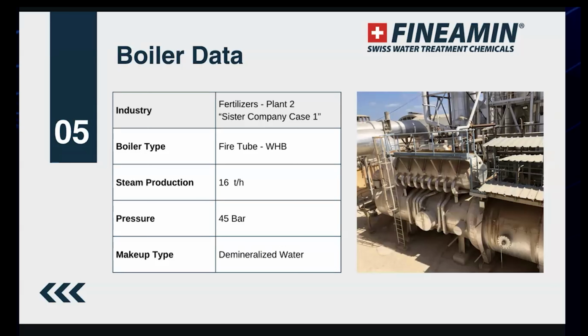Mustafa: Well, if you let me extrapolate the question, if I understand it from a different perspective. If the question is generally about overdosing, there is always a concern about something called gunk formation, or a kind of polymerization, some polymeric structure that will be happening. The good news is that in our general product formulation we are not using octadecylamine, with no offense. Octadecylamine is known as one of the film-forming amines dating from the 1970s. Definitely, if you compare octadecylamine with the other types of film-forming amines, octadecylamines are considered monoamines, and they are more prone to gunk formation when they are overdosed.